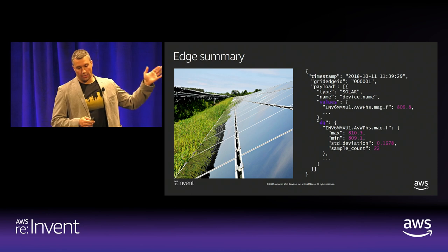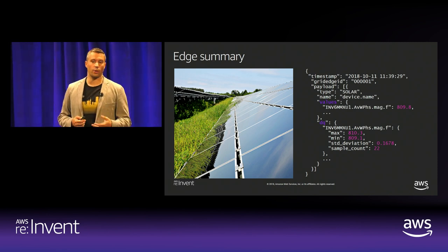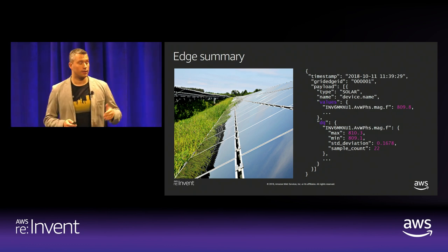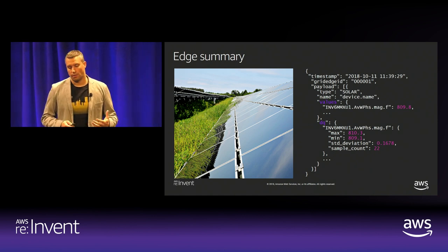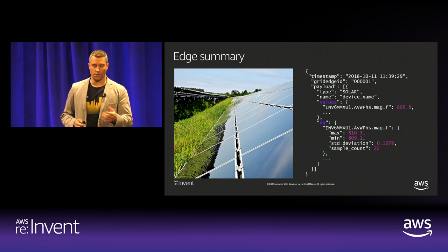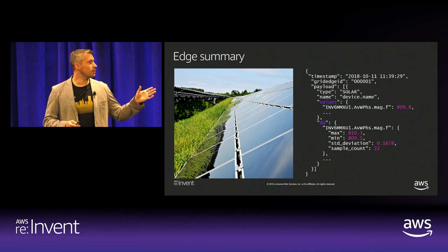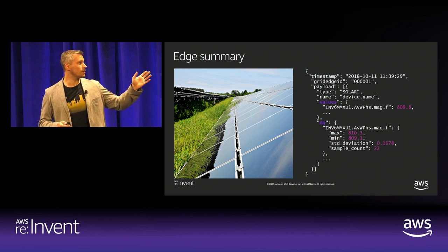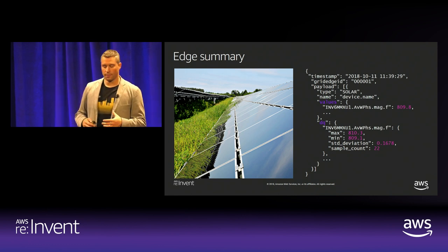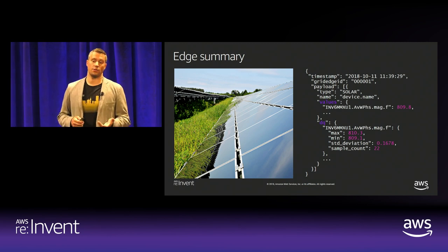And you can see we have a section with the value of a certain field. We're sending the average over that 1 minute period, for example. And then below we have a DQ, which is data quality, a set of tags, a set of metrics that are associated to that specific reading, as I mentioned: standard deviation, maximum, minimum, and things like that. And one thing I didn't get into in too much detail yet is that the name of that field is a long string of characters separated by a few dots. This is the IEC 61850 data model that EDF is using.